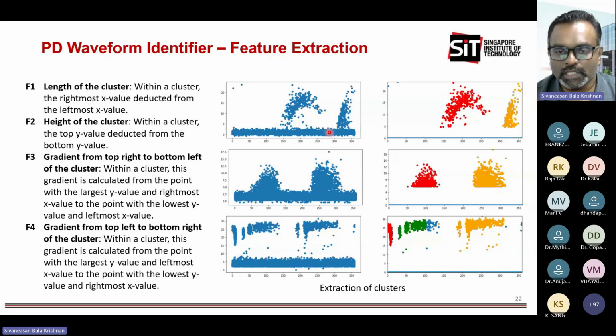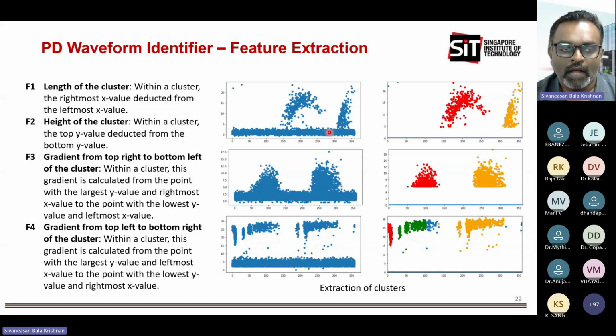We had 450 plus phase resolved partial discharge, or PRPD, plots—these are 2D plots obtained from our partner Singapore Power, our utility company. Out of these, 340 plus were negative PRPD plots, meaning there's no PD, and 110 of them were positive PD, meaning the PDs look like this.